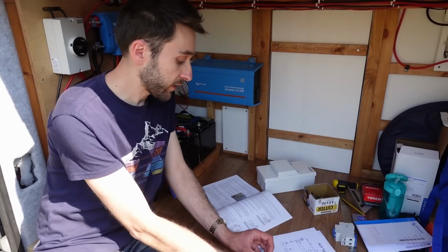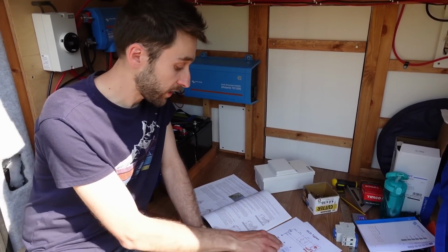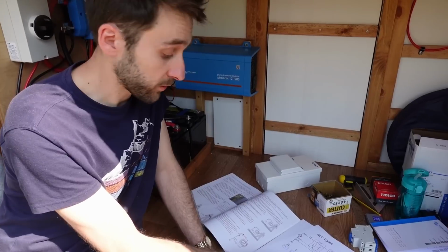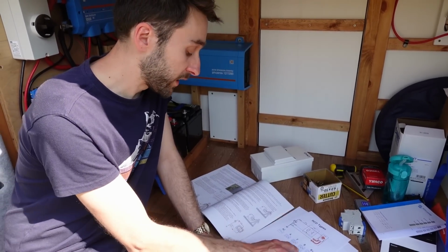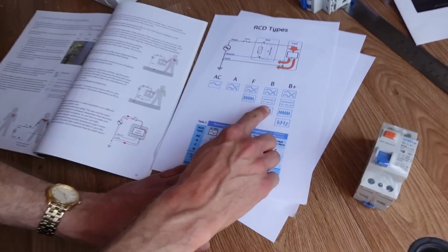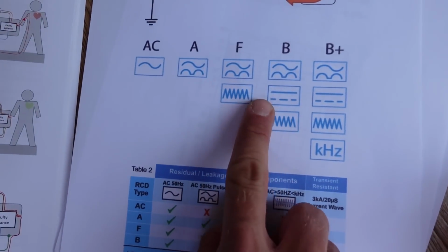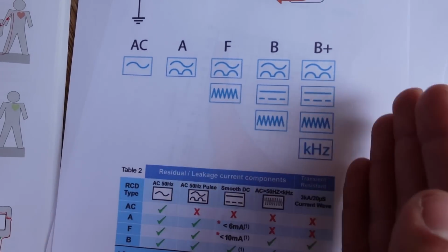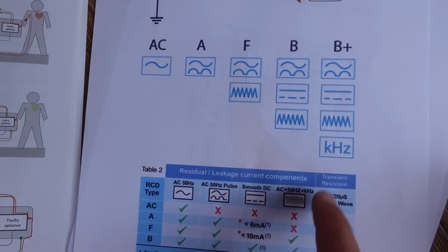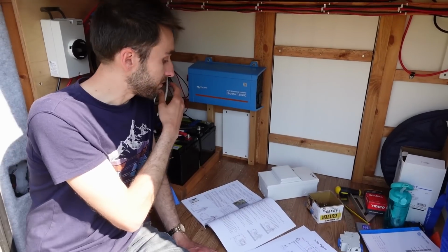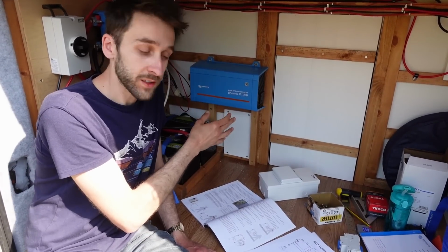But if you have something that has a higher frequency, then potentially the RCD might not detect that. So F allows you to detect really high frequency stuff as well. And then you have B, which can detect actual full DC current. And then B+, which is a little bit rarer and goes on to detect even more stuff, really high frequencies. So we were thinking maybe we'd put a type B RCD on there, which detects obviously the DC current.